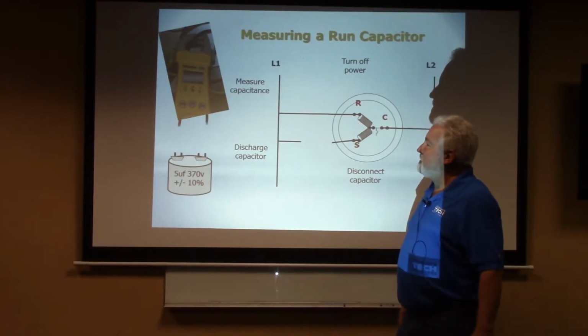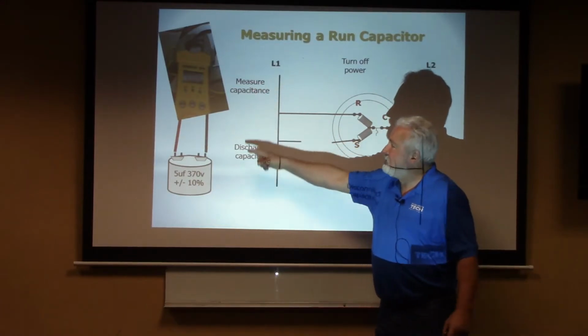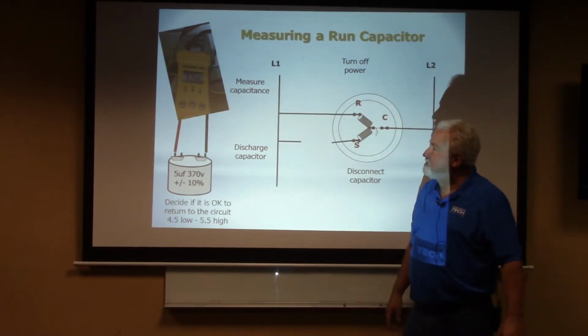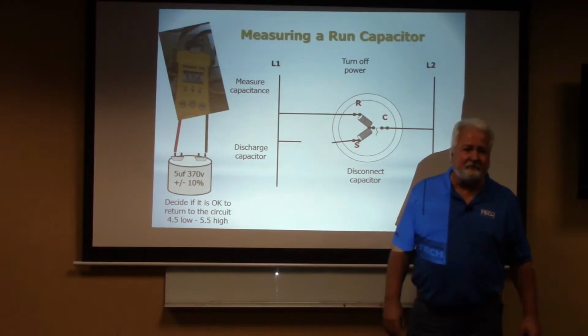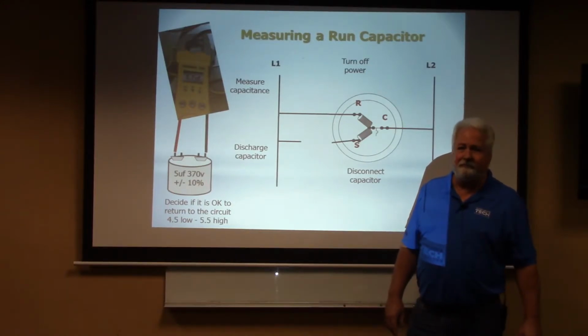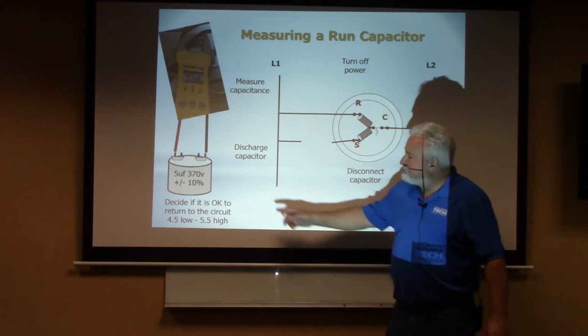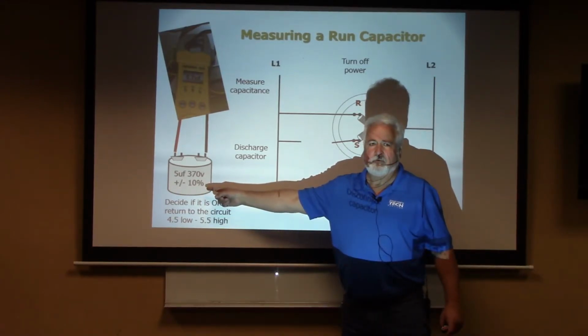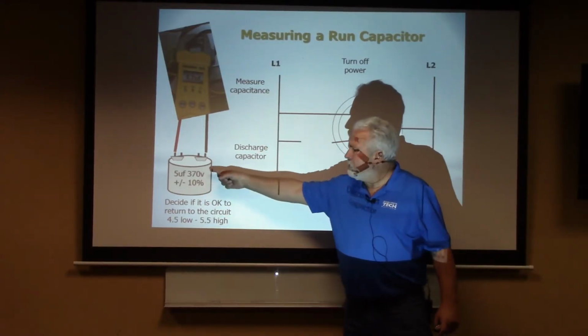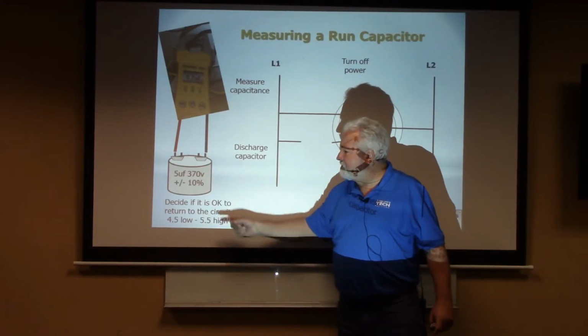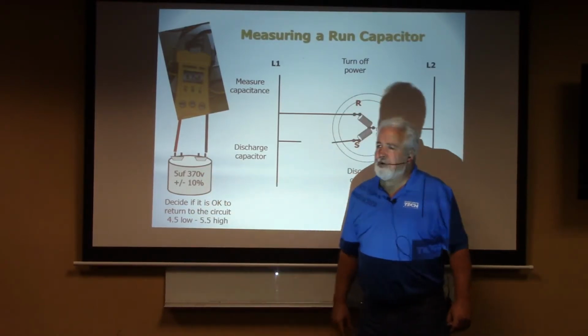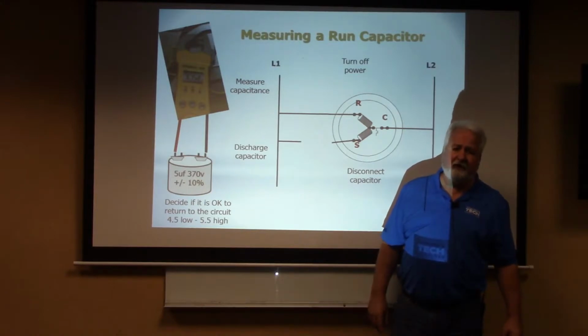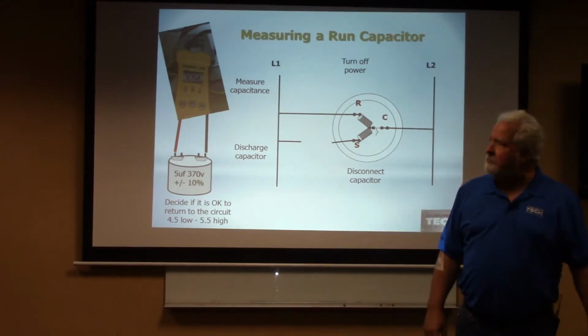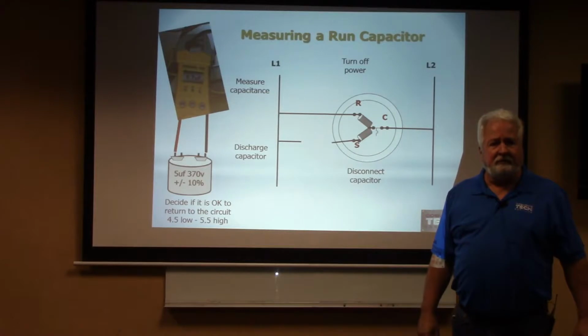All right. So when you do that, you're going to measure the capacitance. You're going to put it on capacitance. You're going to put it down there, and it says 5.7 microfarads. How good is it? Good, right? Yes, sir. Let's see. It says plus or minus 10%. Here's the math part. 5 microfarads plus or minus 10%. So that means 4.5 on the low end, 5.5 on the high end. And we measured 5.7. It's not good anymore, is it?